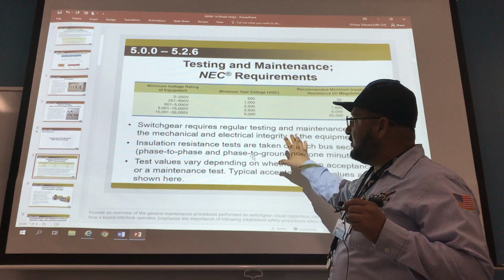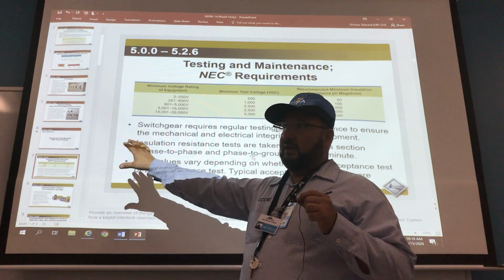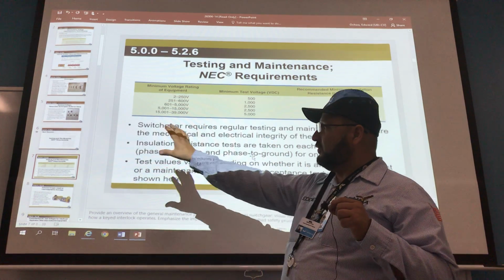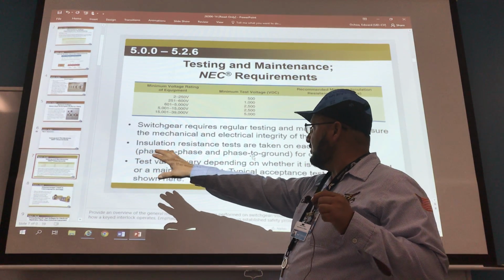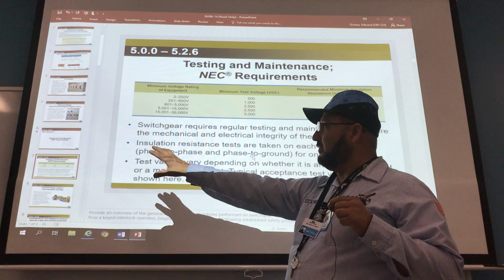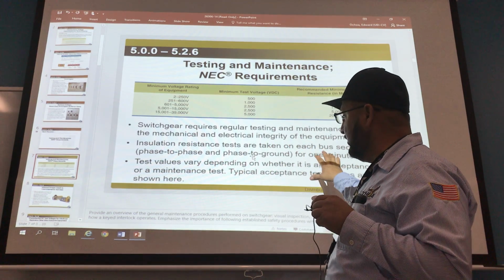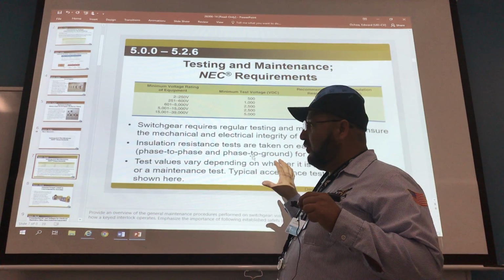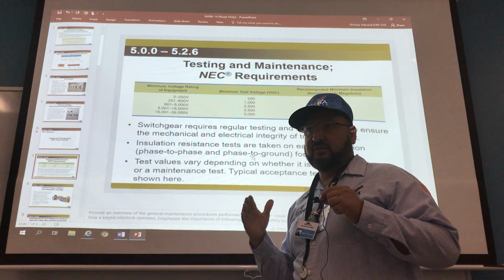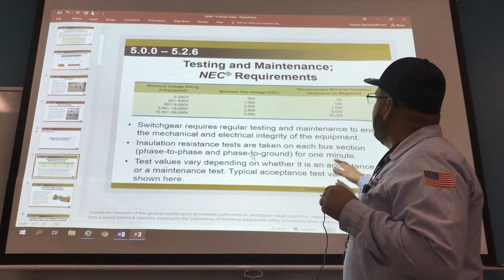A lot of times there's zero reference, so you got to establish a reference. You can establish a reference from this switchgear to the next switchgear. If this switchgear over here is so many ohms or voltage or amps, and this one's a little bit different, you got to see what's normal. So you got to establish a normal point. So this is what this is doing.